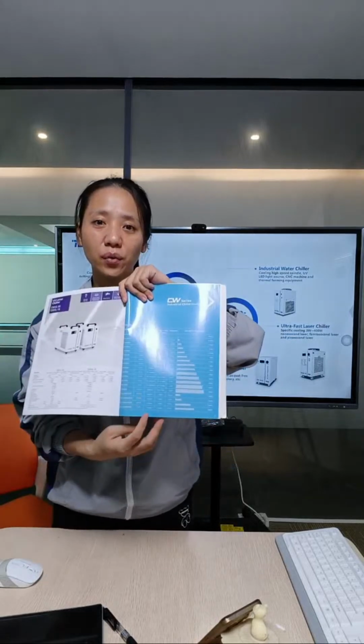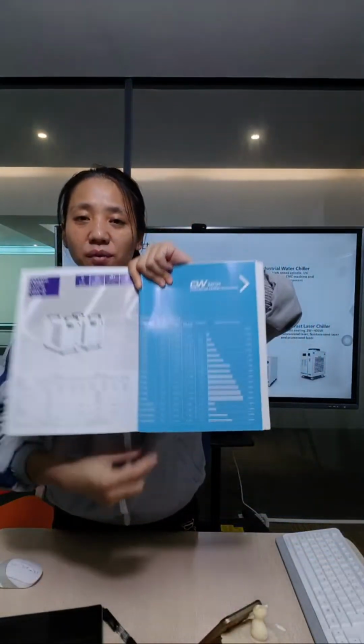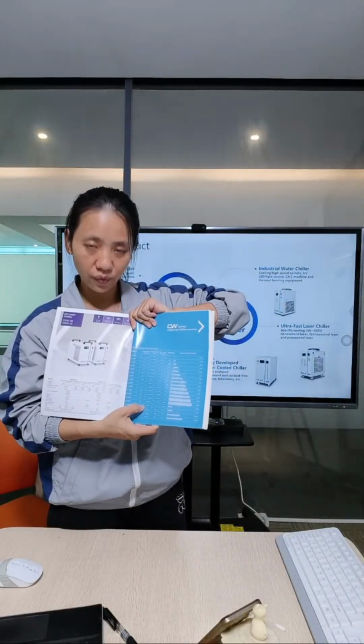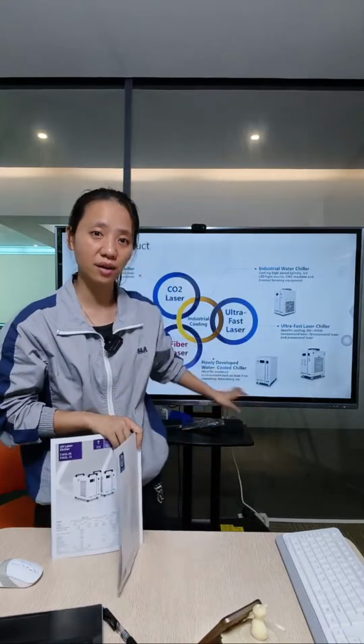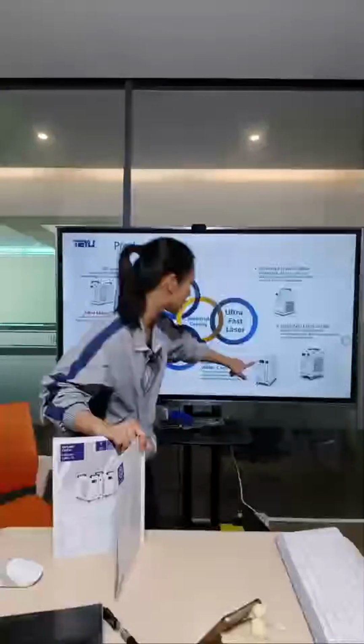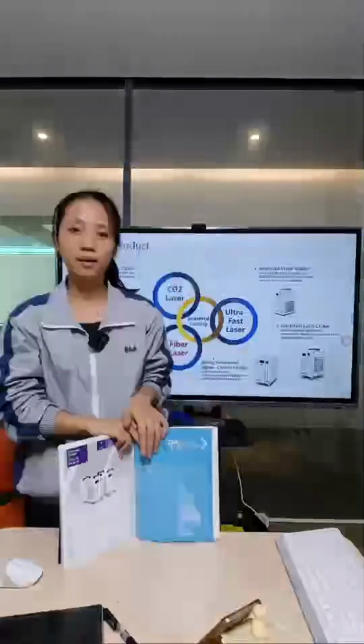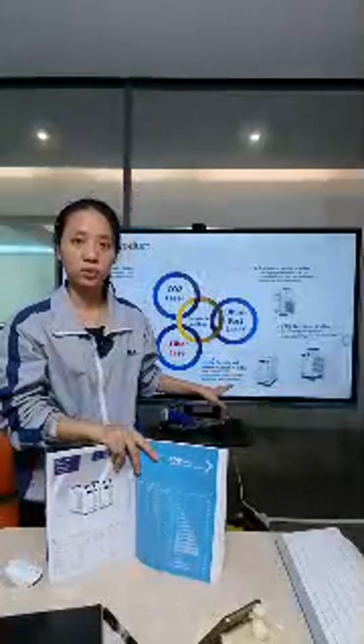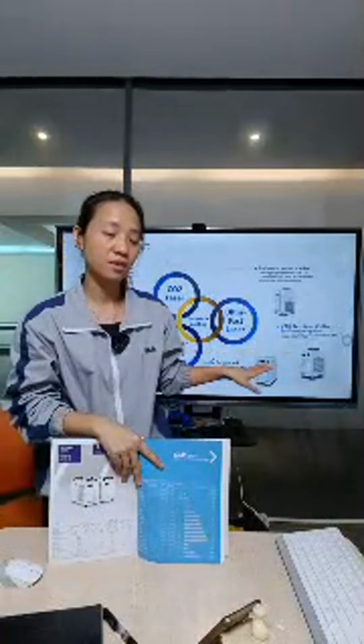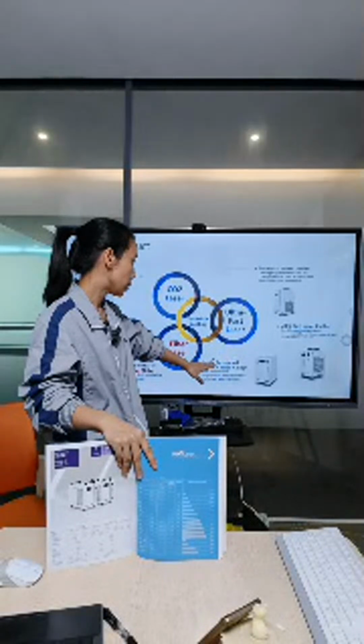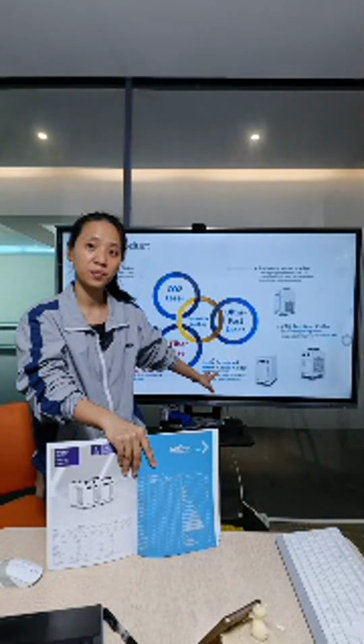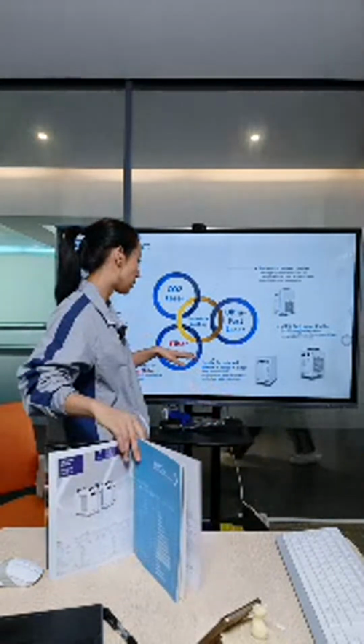In this series, at the bottom, we also have another one without a fan. It looks a little different from the outlook — you can see it has no fan inside. That is the water-cooled water chiller. Before, I told you all the other series are air-cooled, but this one is water-cooled. This series is special and suitable for dust-free working environments, because some laboratories or dust-free workshops have strict requirements on airflow and noise.